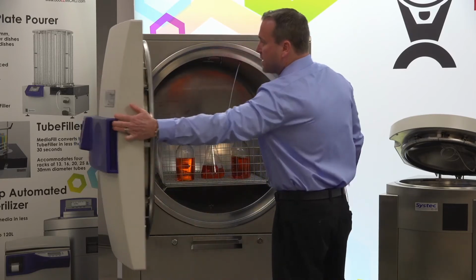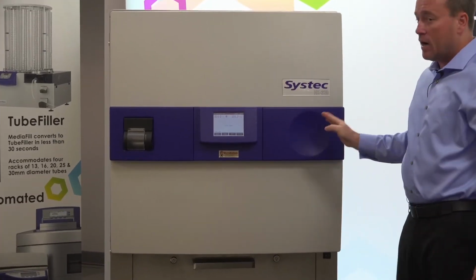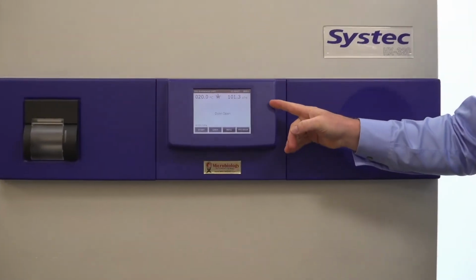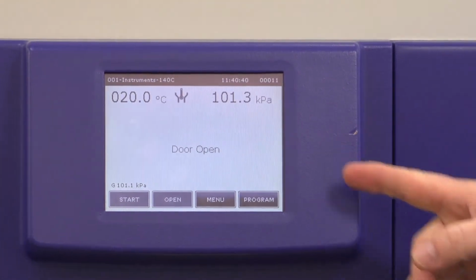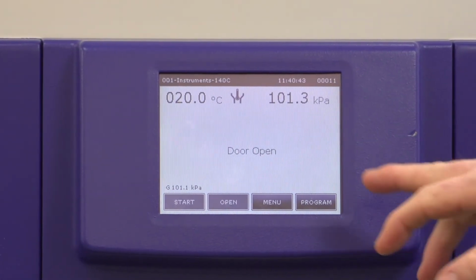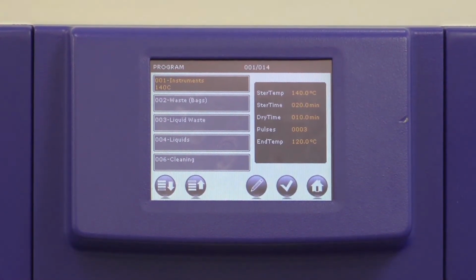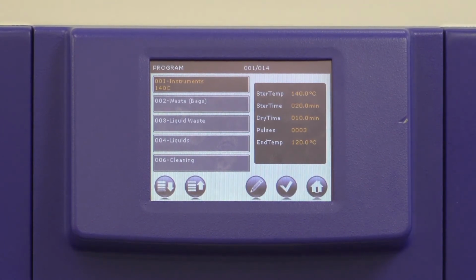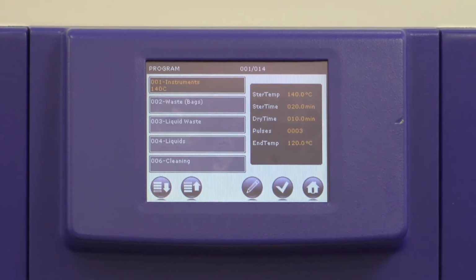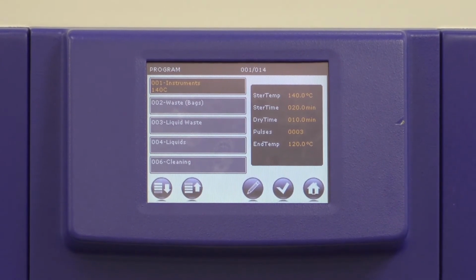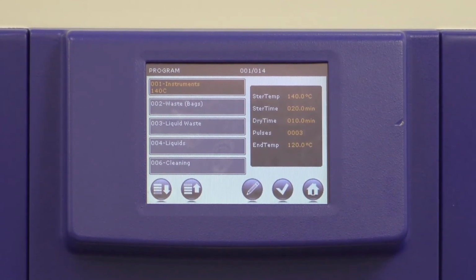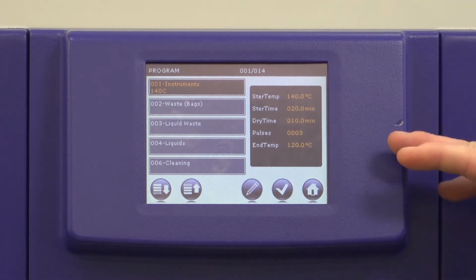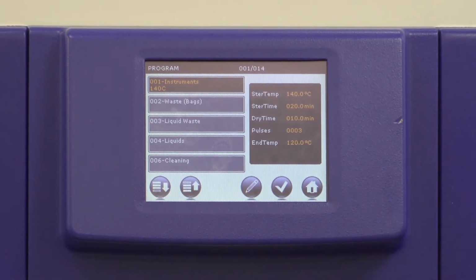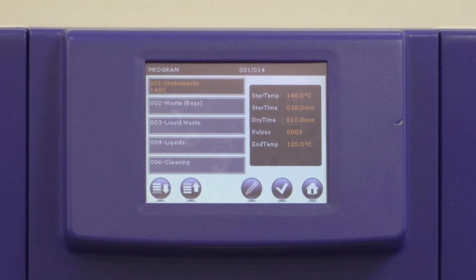So as we mentioned, the HX series has a touchscreen control. So all of the control systems can be accessed directly here. So a really easy system. We can go to program. We can look at the different programs that we offer. Every instrument that we have is going to be a layout of programs of instruments, waste bags, liquid waste, liquids, and then a cleaning cycle. On the HX series instruments, we can enter up to 99 different programs. So if you did have a different type of waste bags that you wanted or multiple liquid cycles, we can program those in so you can just access those.